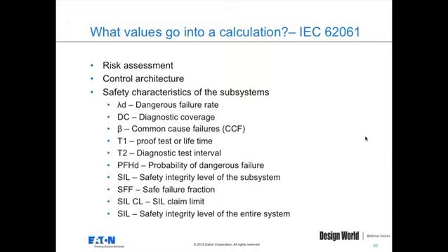Diagnostic test interval, so how long between tests are all the components being tested. Sometimes that diagnostic test happens when the machine shuts down and comes back up. Sometimes it happens periodically through its operation. The probability of a dangerous failure, so how probable is it that some type of dangerous failure is going to occur based on the reliability of the components.